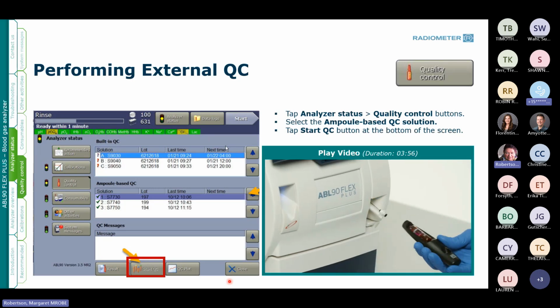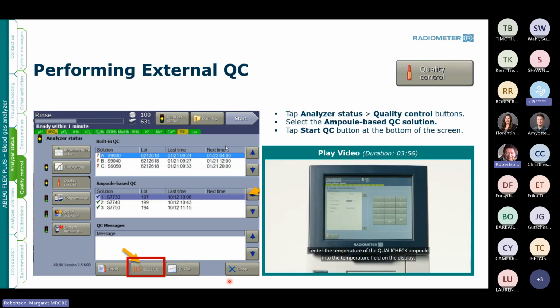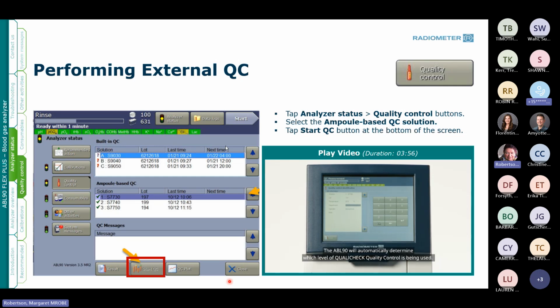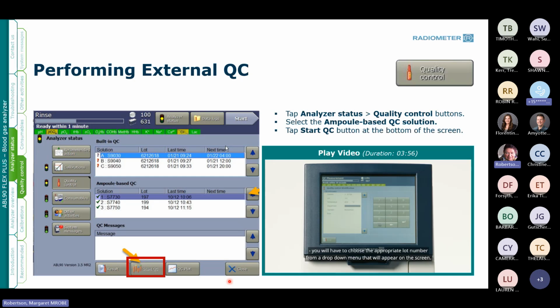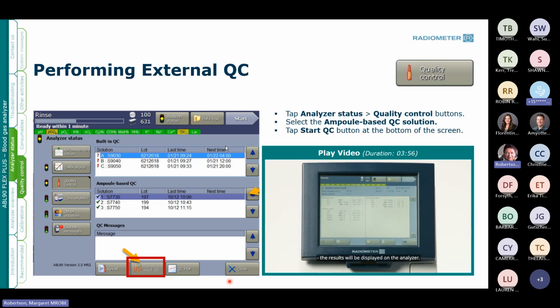Remove the adapter, and if necessary, enter the temperature of the QualiCheck ampoule into the temperature field on the display. The ABL90 will automatically determine which level of QualiCheck quality control is being used. If more than one lot number for the same level of QualiCheck quality control is stored on the analyzer, you will have to choose the appropriate lot number from a drop-down menu that will appear on the screen. Once the QualiCheck measurement is complete, the results will be displayed on the analyzer.